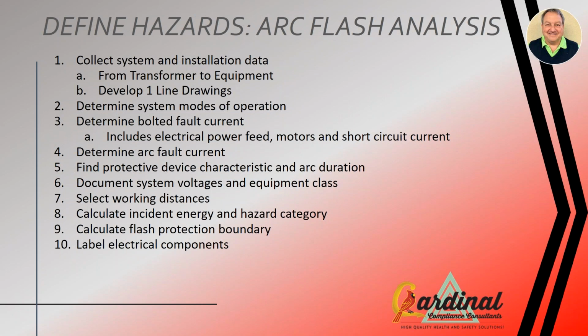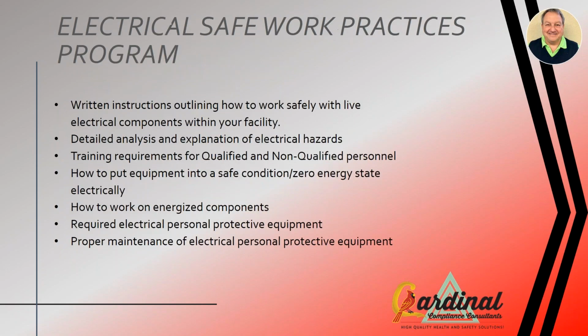Sometimes that arc flash boundary can be quite significant on your incoming category 3, category 4 power panels. 10 feet, 12 feet, even up to 20 feet. That arc flash could extend out to the panel and provide a level of energy that is a hazard. OSHA defines that at 1.2 calories per square centimeter. Then after you've got all your analysis done, as I said, they don't want electrical safety to be a memory game. They want you to label your components so that the voltage is known and the arc flash is known and what type of arc flash category you're looking at.